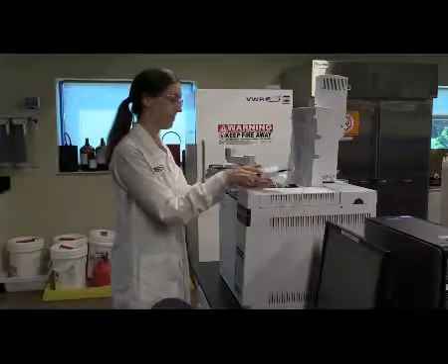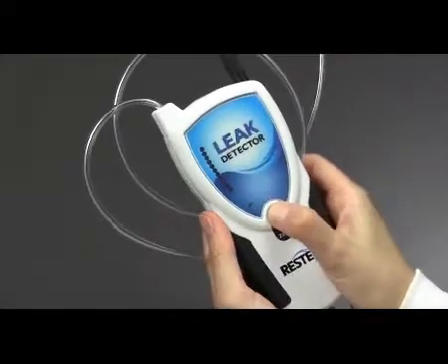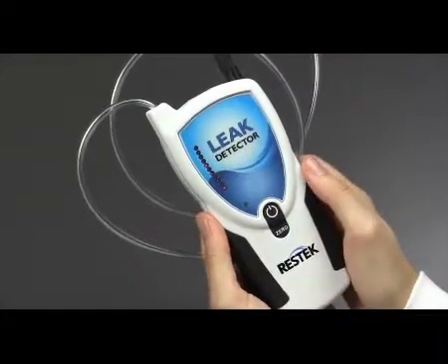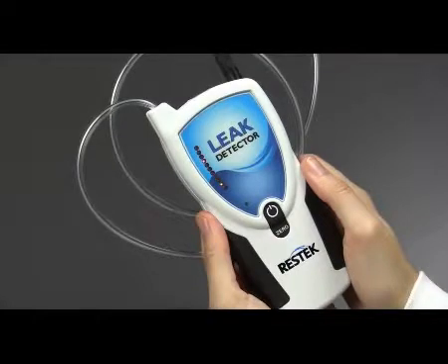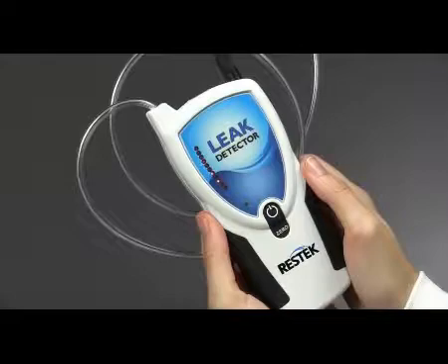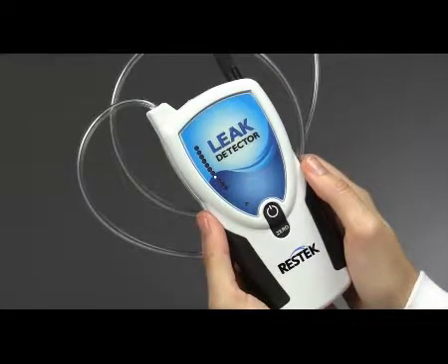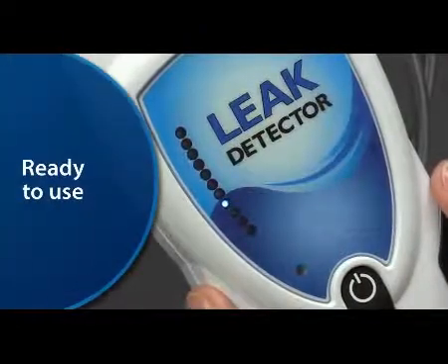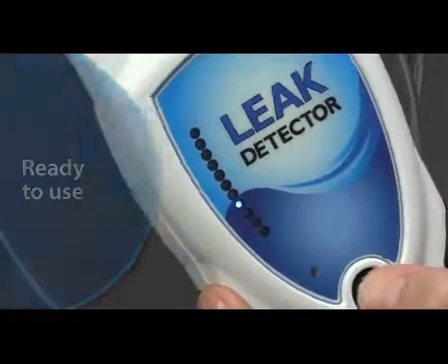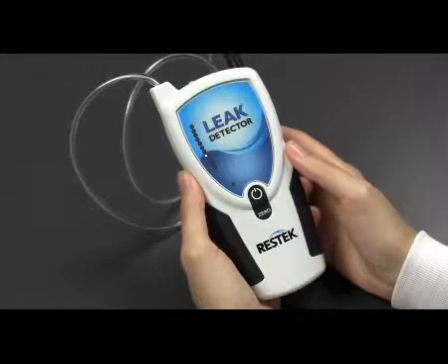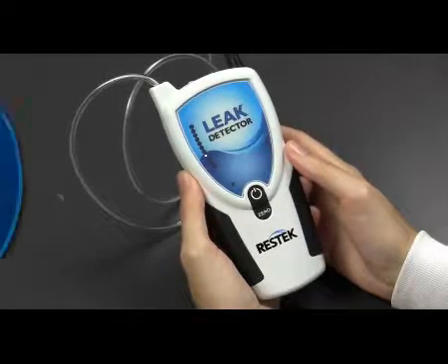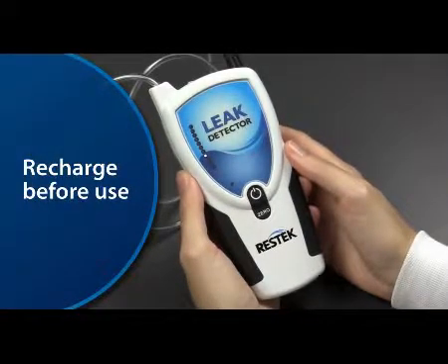If this is your first time using your leak detector, fully charge the battery before use. Before using your leak detector, first turn the unit on and wait for around 15 seconds for it to stabilize. Then, check that the battery has a sufficient charge. If the blue LED is lit but not flashing, your unit is charged and ready to use. If the blue LED is flashing, the detector's charge is low, and you need to recharge the unit before use.